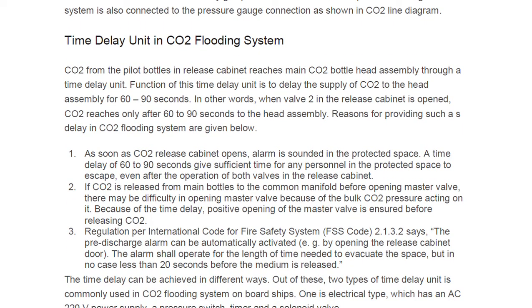Now we have the time delay unit in the CO2 flooding system. This is extremely important because it is directly associated with the safety of human life. CO2 from the pilot bottles in the release cabinet reaches the main bottle head assembly through a time delay unit. The function of this time delay unit is to delay the supply of CO2 to the head assembly by 60 to 90 seconds.